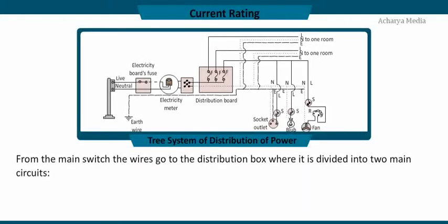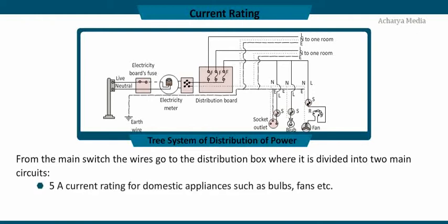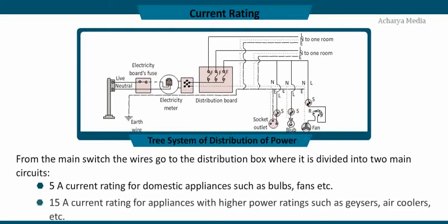From the main switch, the supply goes to the distribution box where it is divided into two main circuits: one of 5 amperes current rating for domestic appliances such as bulbs, fans, etc., and another of 15 amperes current rating for appliances with higher power ratings such as geysers, air coolers, etc.